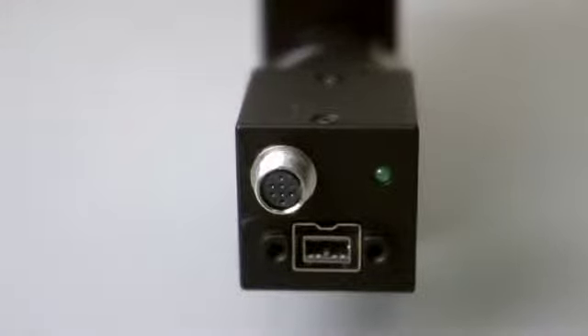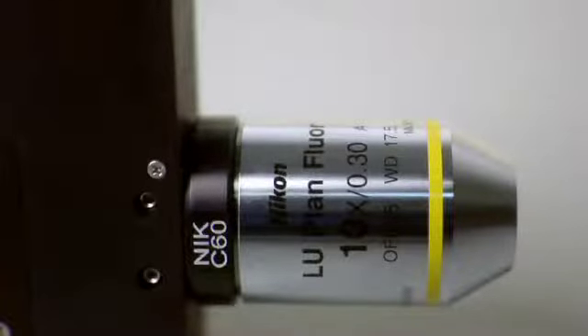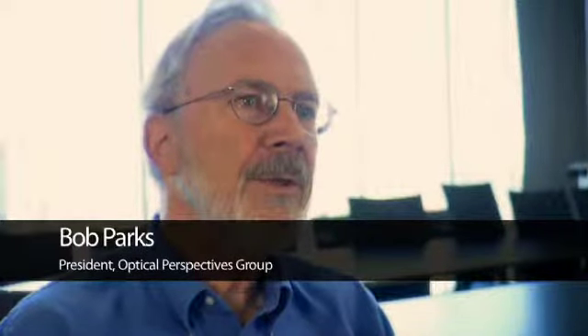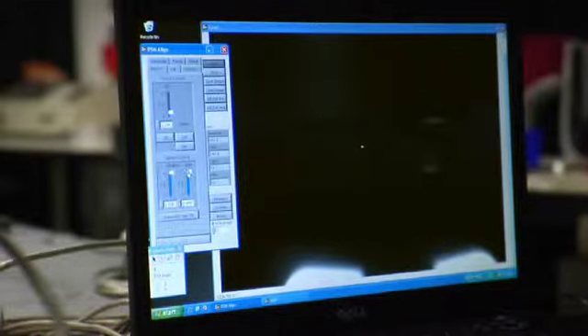The PSM stands for point source microscope. It effectively creates a point focus at the objective, which gives you essentially a perfect wavefront coming out of the microscope. And then when it's reflected off a center of curvature of an optic, if the optic is essentially perfect, it comes back as a very tight, well-focused spot, which you then see on the video screen.